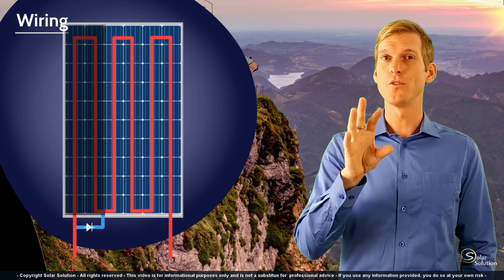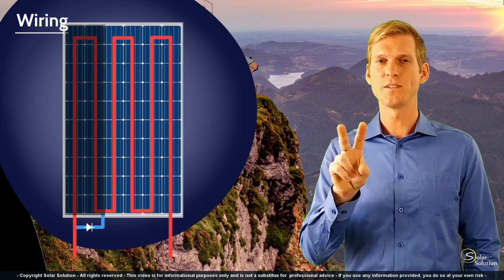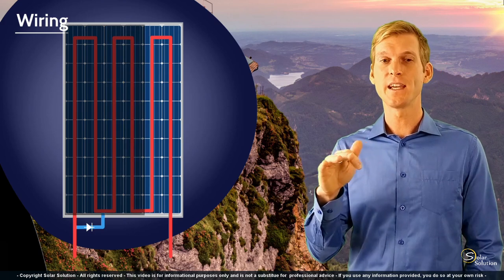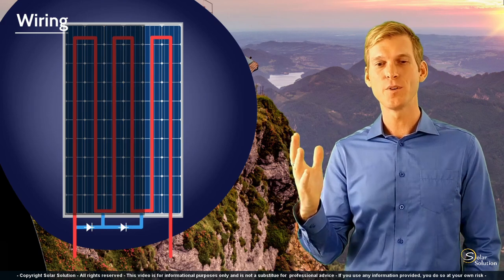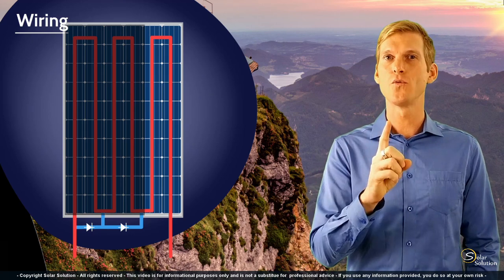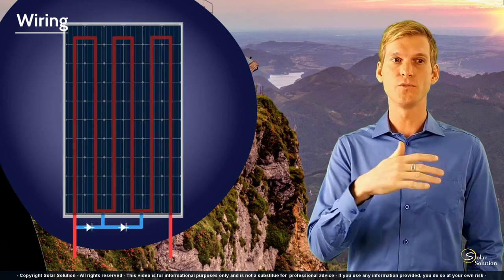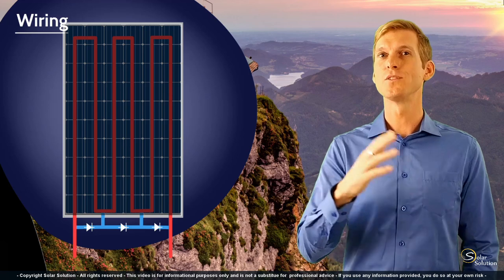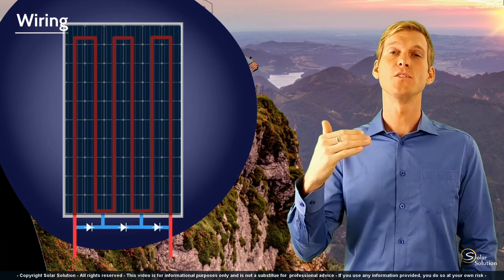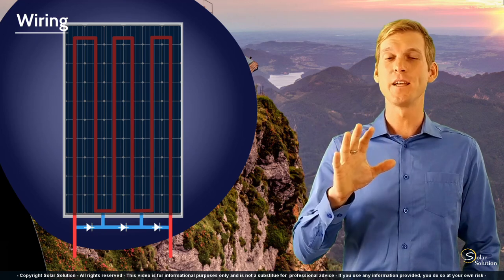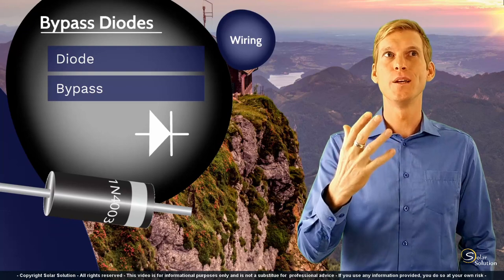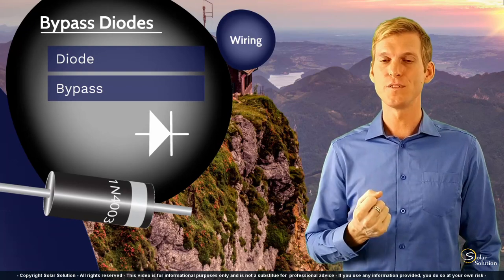Most panels have two or three bypass diodes. If a second section of the panel is shaded, another bypass diode kicks in, allowing the remaining part to keep working. The main message: without bypass diodes, one bad cell would shut down the whole panel. With bypass diodes, only the affected section is cut off and the rest of the panel still performs. This significantly increases the overall stability and performance of your solar system.